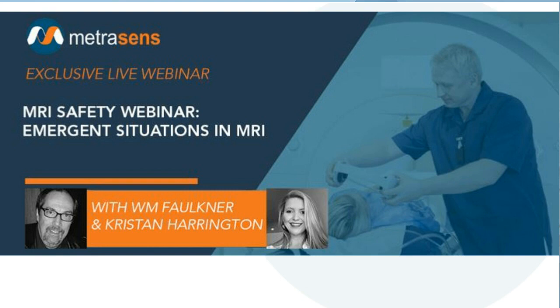You showed some photographs of incidents causing burns. Do you know if the burns from the electrodes had the wires attached? That picture was given to me by Frank Shellock, and no, the wires weren't attached — but it doesn't matter if they were. If they were attached, they shouldn't have been on there at all. Those were ECG electrodes that came down from the floor with the patient. It really doesn't matter whether the leads are on or not. Bottom line is, you don't want anything going into that magnet that you don't need, that you don't know what it is, and that is not designed specifically for the MRI environment. I don't care if the nursing staff wants to leave the electrodes on — they're not staying on when I go to put them in the magnet.